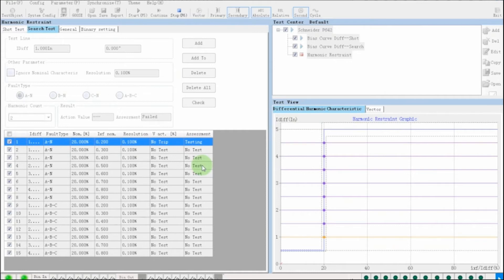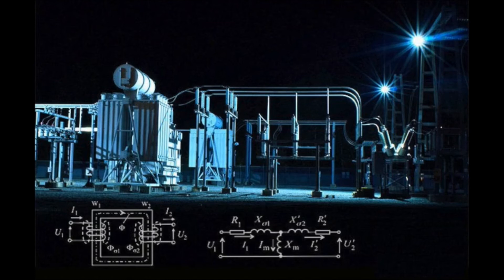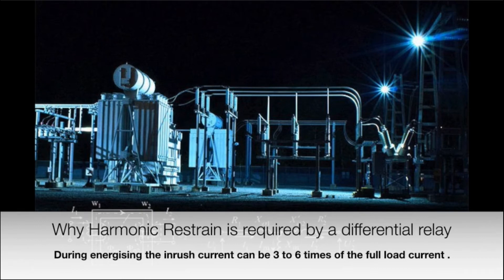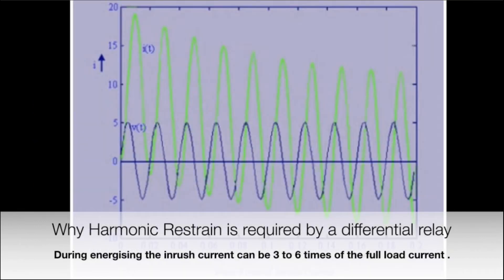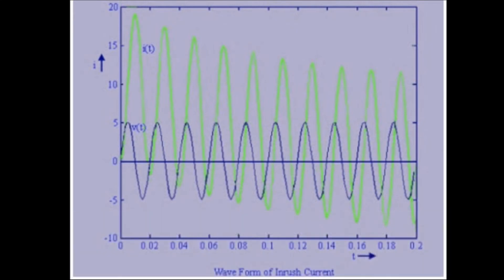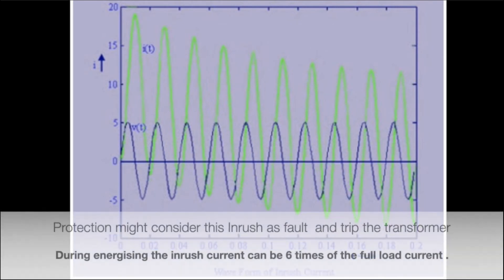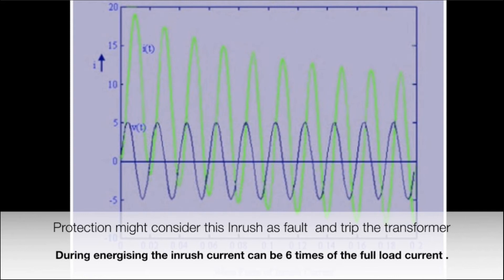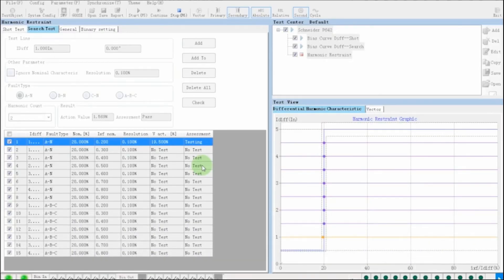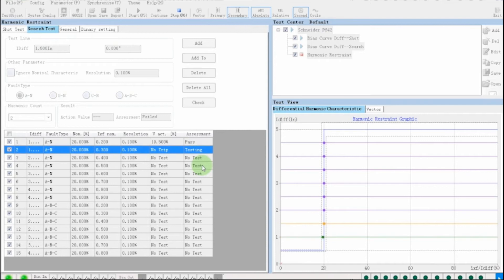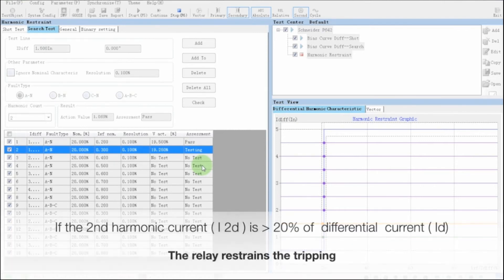While the test is proceeding, let's brush up our few concepts on differential harmonic restraint. Suppose we are going to energize a transformer. Transformer will have inrush current, which is around three times of the full load current. So what we need to do for preventing differential protection operation due to inrush current? This requirement calls for harmonic restraint in differential protection of transformer.